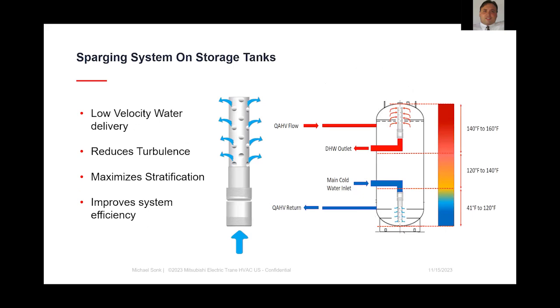So again, this just kind of graphically depicts what these sparge fittings are that I mentioned that are important to be incorporated into these tank designs. This is more of a generic depiction of this, but it represents kind of the goal and the strategy you're trying to achieve with these fittings. And again, that is to minimize mixing inside of these tanks and maintain a nice thermocline through the tanks. We want to see that stratification. We want to maintain hot water up near the top of the tanks and keep the cold water contained to the bottom of the tanks, to that heat pump water return or that separation heat exchanger.